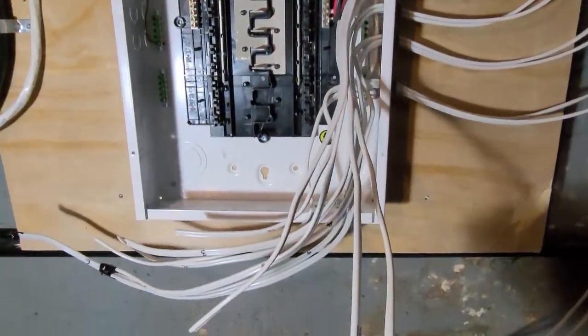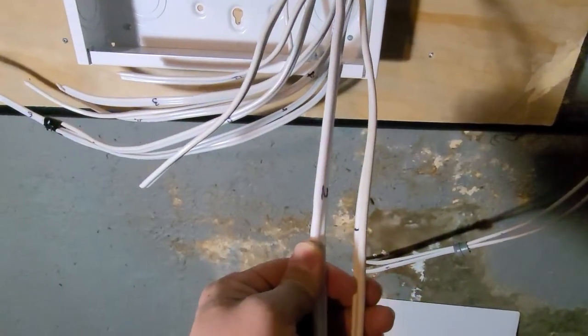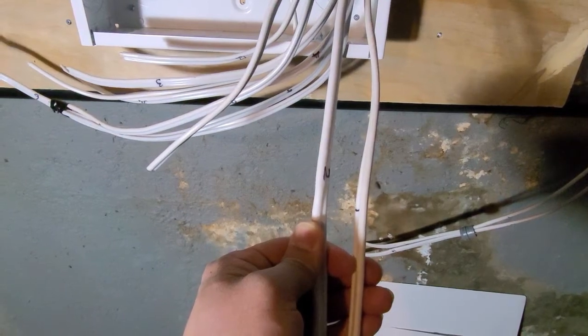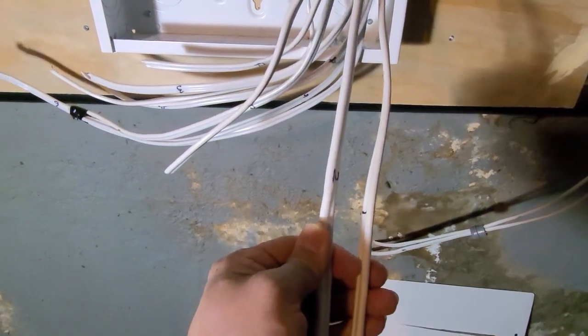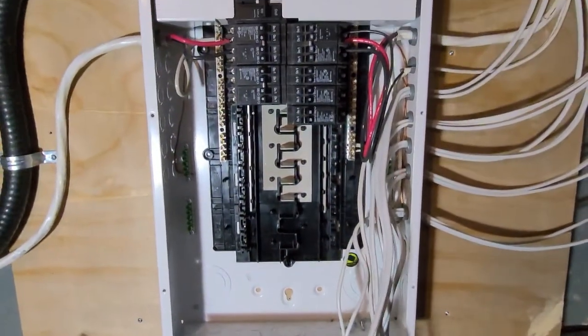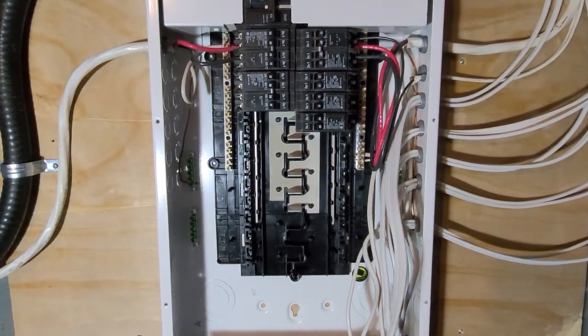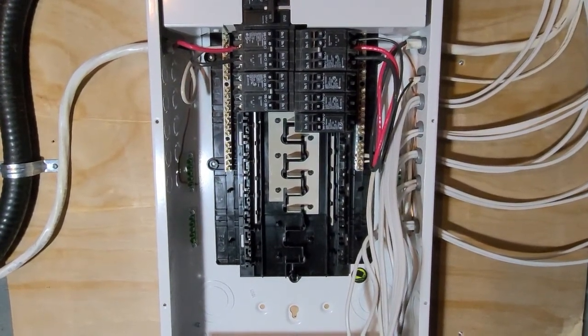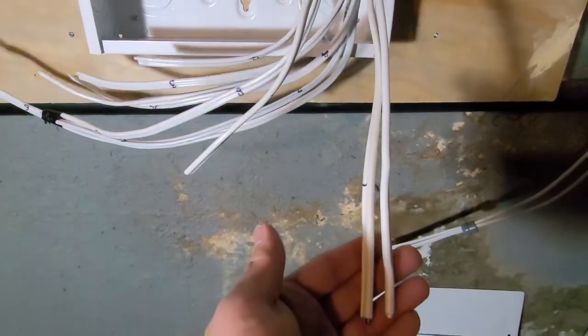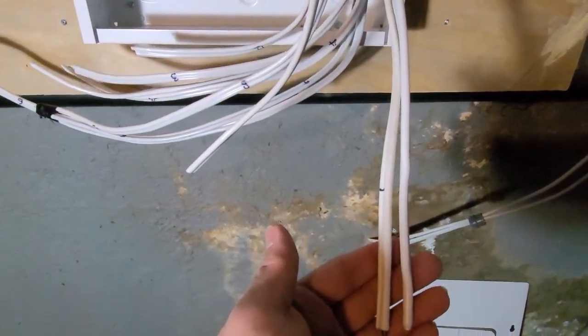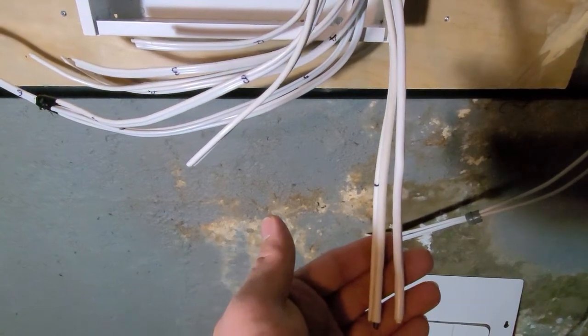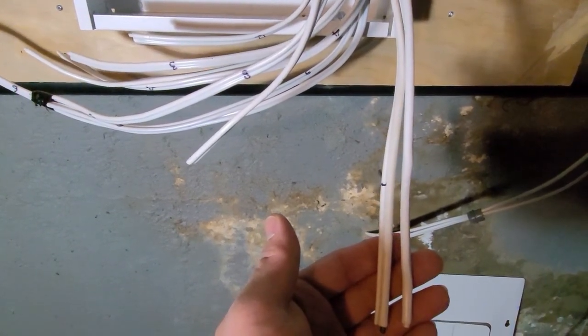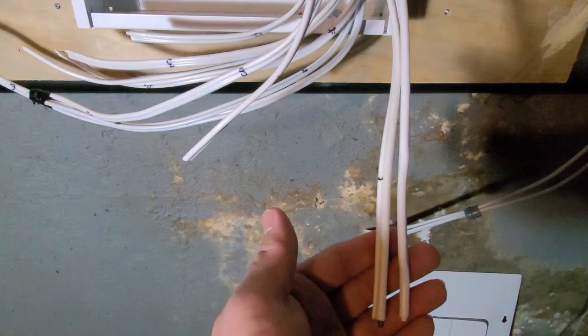and it will secure the cables here, no problem. And on our new panel side here, I got wire number 1, number 2. I need to temporarily terminate those two into the electrical panel, so the customer will always have power there. But we have to make sure we have long enough, not only the hot, but also the neutral. Because this is a very old panel and doesn't mark anything about which circuit is which.